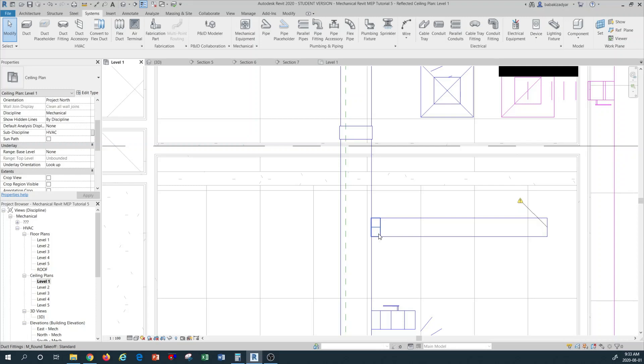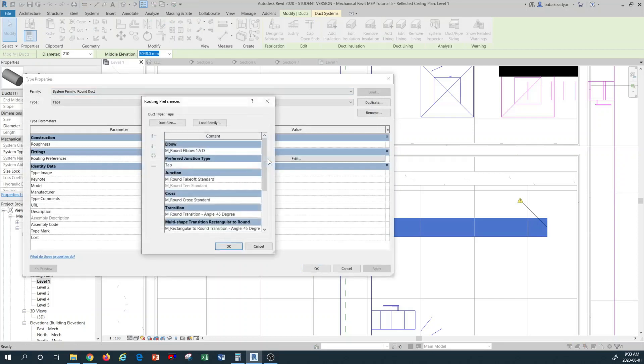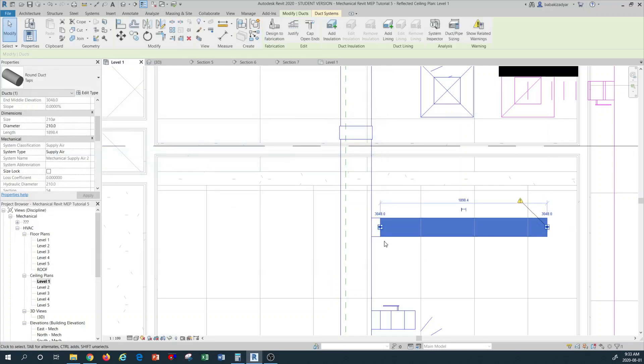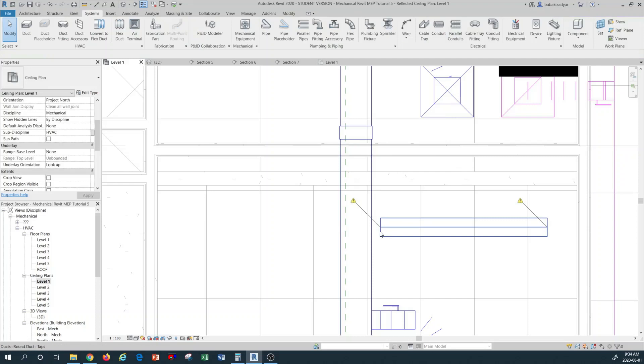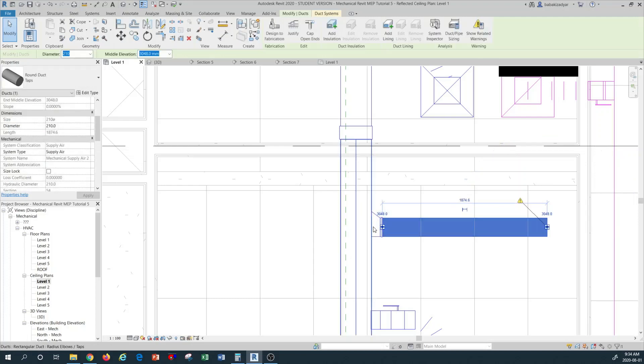Note that you don't change the fitting itself — you change the duct that needs to connect to the main duct. The property of this branch duct and its connection property needs to be changed. Highlight the duct, go to Edit Type, go to routing preference fitting, and in the junction setting change this to round takeoff shoe standard. Click OK and Apply. It doesn't affect already drawn ductwork, but if you delete this branch and reconnect it, you see the new fitting type is applied after changing the junction routing connection setting.